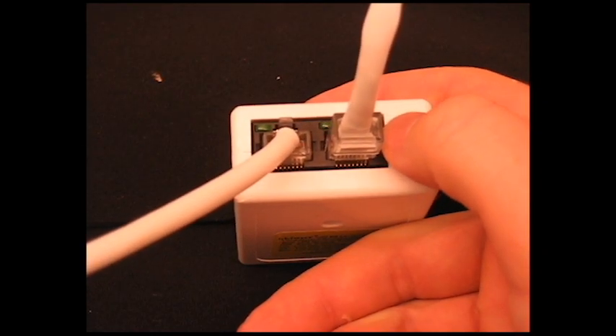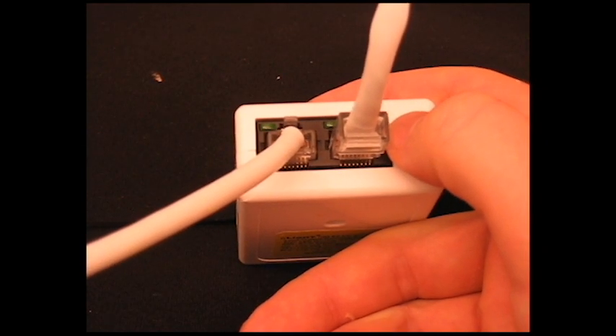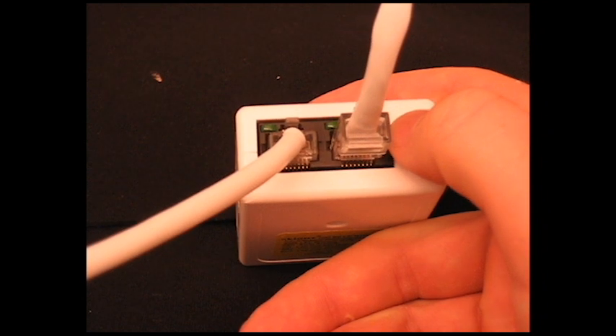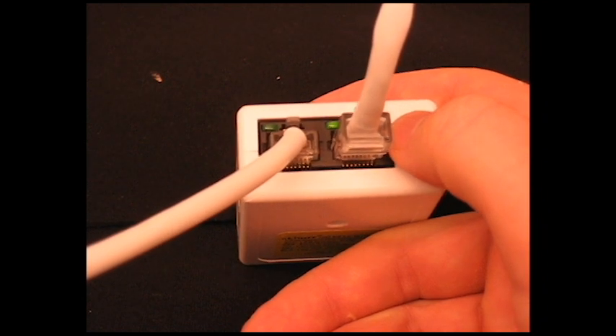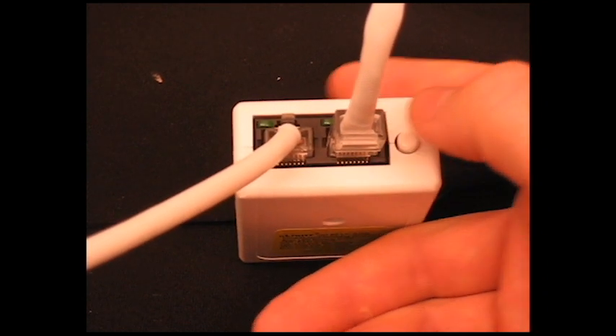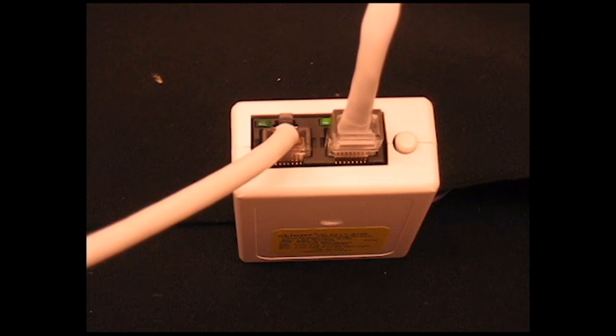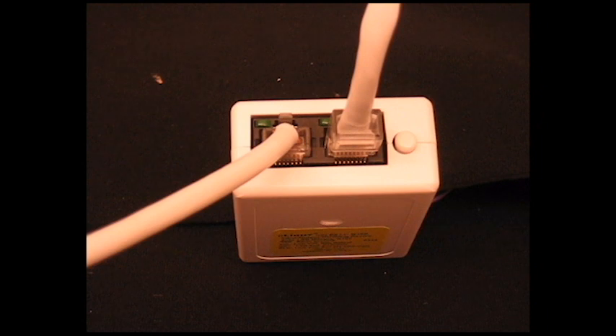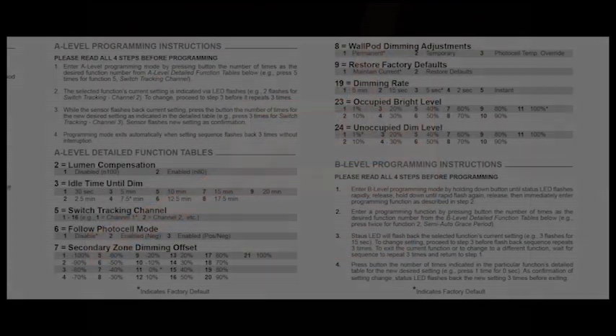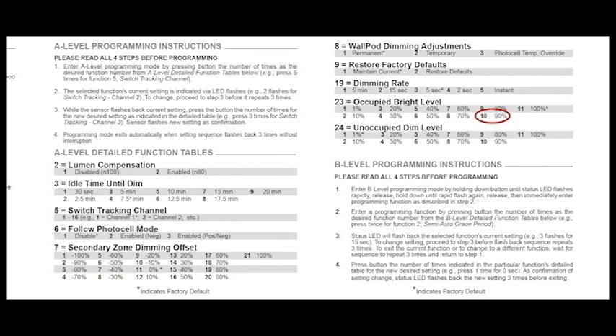Once we enter this initial command, we will see the green LED flash back a specific pattern three separate times. The number of flashes per group will correspond to the selected function's current setting. We can see that the device is flashing in groups of 10. If we refer back to the detailed function tables in the instruction booklet, we can see that the number 10 underneath Occupied Bright Level corresponds to 90%.